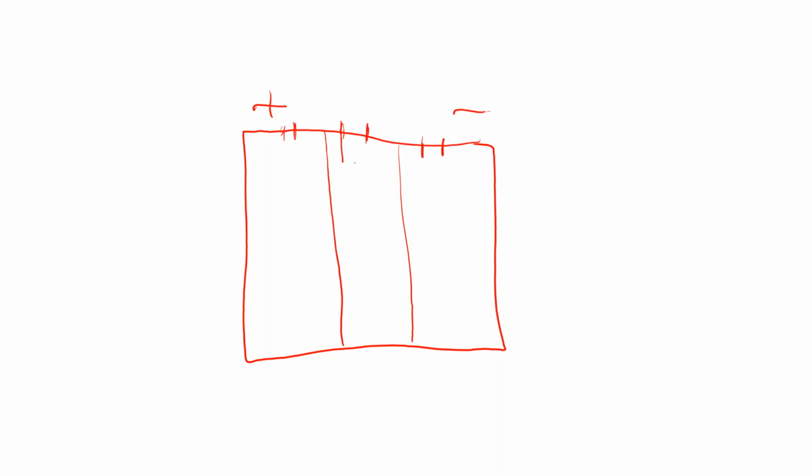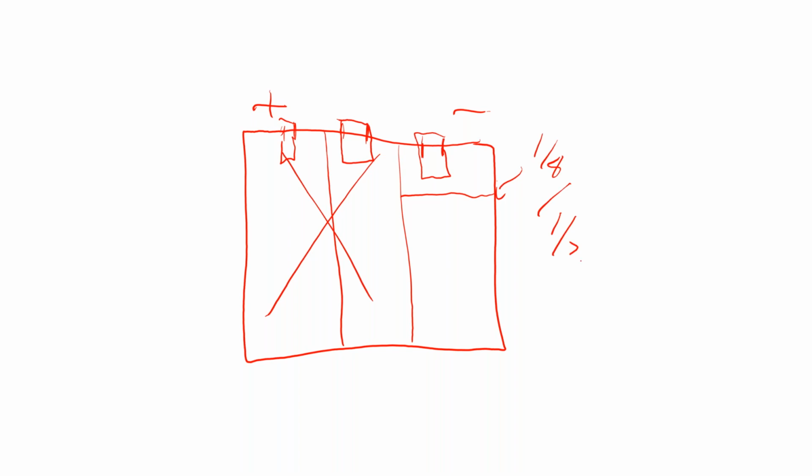Not the best drawing in the world, but that is what's called the vent well, okay? The vent well on the Series 5000 batteries extends about an inch into the battery bank, okay? About an inch into the battery cell itself. So let's say this is the vent well. Let's just talk about this one here, so it's a better drawing. The water level should never come closer than, so this is the water level, 1/4 inch to 1/2 inch from the bottom of the fill tube.